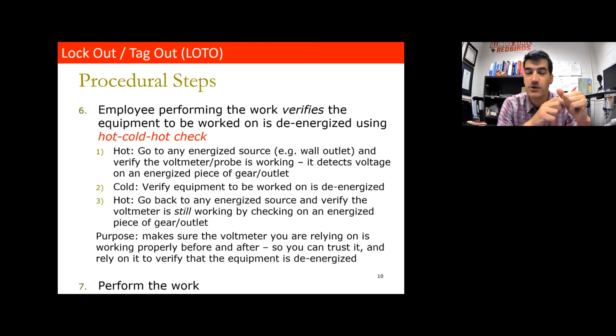To perform a hot, cold, hot check, you'll be working with a multimeter, voltage probe, or something that detects voltage. You need to make sure the equipment you're working on is de-energized -- making sure you didn't miss anything. It's a last check before you put your hands in there and start working, to make sure there's no voltage and you won't shock yourself.